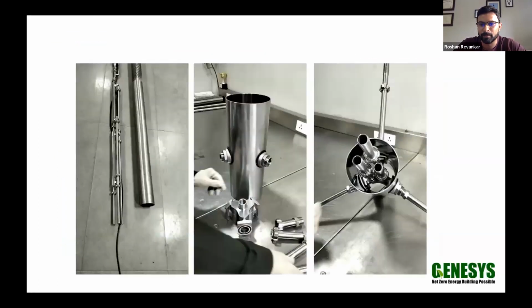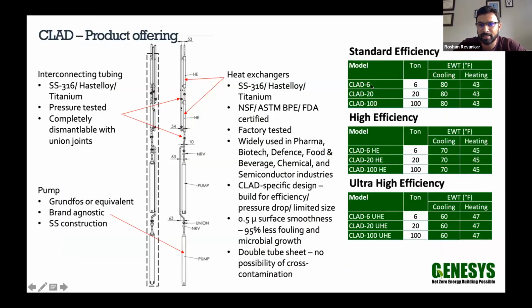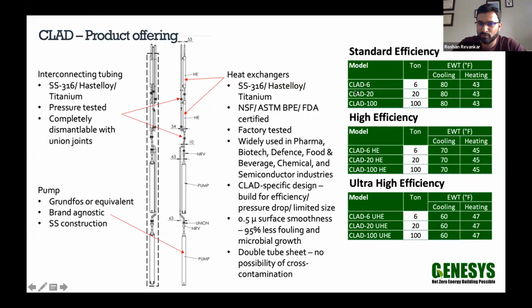Let me go back a few slides to this particular slide. CLAD 6, in terms of diameter of the borehole: for a 6-ton CLAD unit, we only need a 5-inch well or a 5-inch casing. For a 20-ton model, we need a 6-inch casing. And for the 100-ton, as you can imagine, there are bigger pipes and bigger flow, so we need a 12-inch casing. The 50-ton CLAD that will be available later this year will need a 10-inch casing. So we're talking essentially 5, 6, 10, and 12-inch for each of these models. We are working with a lot of projects where they currently have water wells which are either 5 or 6 inches, and the CLAD unit can go right into that and connect to a heat pump if they were to move to a heat pump system.